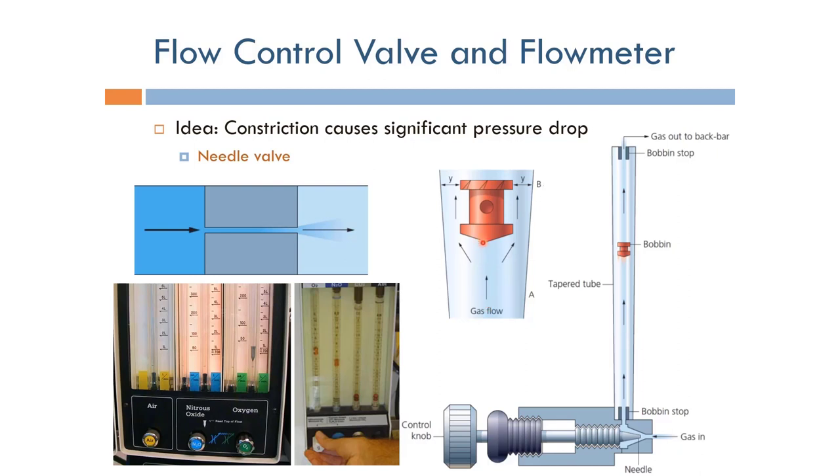We can have different markings here on this tapered tube so that we can know from the location of the bobbin the flow rate value. We adjust the one responsible for the nitrous oxide and the one responsible for oxygen, and we can actually adjust the mixing ratio between the two.